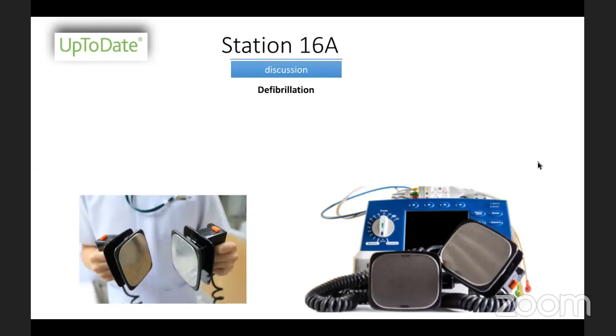What is the difference between pads and paddles? Pads we see in the stations where there is a defibrillator, like in the railway station, they are mostly biphasic, sir. And the paddles we see in this defibrillator. The sticking pads have some advantage because you can be hands-free, and you need not interrupt the chest compressions, and the contact is more consistent when you stick the pads on the chest. Paddles, you have to give adequate pressure. The chest compressing person will have to interrupt more, the interruption time will be more, and you have to apply jelly and give good mechanical contact, then activate the charge button, and before you discharge, you announce to the team, I am clear, you are clear, all are clear, and then activate the defibrillator button.